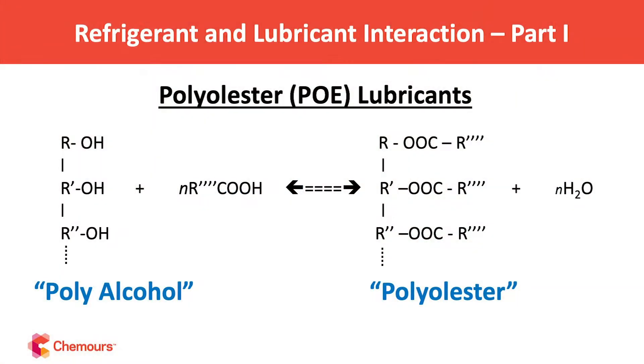That's the basic ester molecule. If we expand that a bit — instead of a simple alcohol with just one OH group, we have a polyol alcohol: a bigger, more complex molecule with many OH groups. That can react with organic acids during manufacturing. All those R, R-prime, and R-double-prime groups show the variety available to fine-tune viscosity grades and properties. When that polyol reacts with the acid, you get a polyol ester — and water is the byproduct. Importantly, notice from the double-headed arrow that this is a reversible reaction. In the next video we'll discuss what happens when water reacts with POE and can drive the reaction in reverse. But essentially, that's where the name POE comes from.